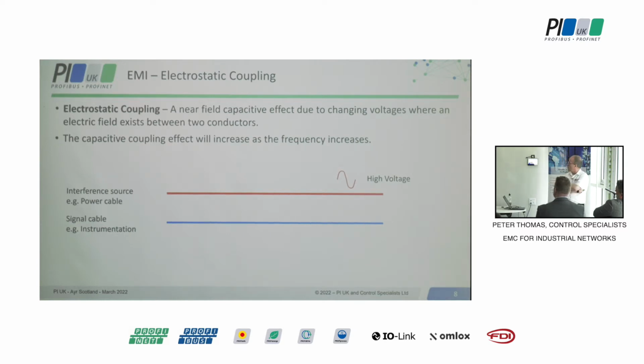If we put a scope on each conductor, first we'll see a sine wave of 415 volts RMS on the red one. But we'll also see a sine wave on the blue conductor, because of capacitive coupling - an electric field is generated between these two conductors. It's a bit like two magnetic poles: you put them together and they move apart, but you can't see what's happening. Here it's similar, except it's electrical. We've got a problem because we see a sine wave on our sensitive signal, and the amplitude of that signal is quite small, so we don't want this to happen.